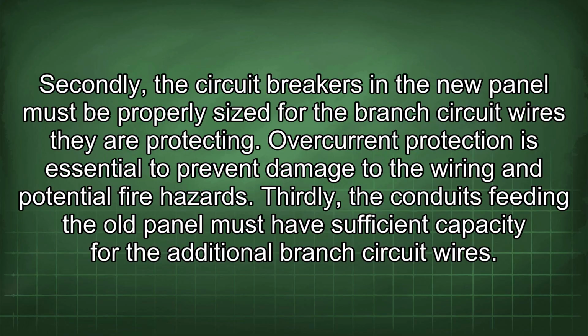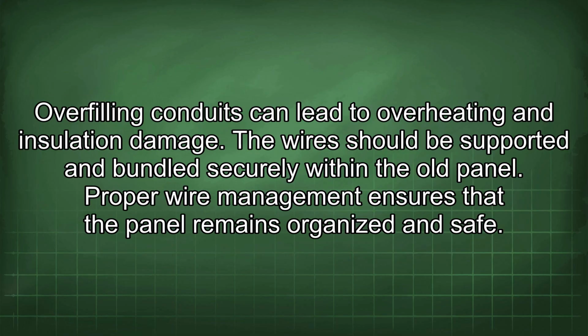Thirdly, the conduits feeding the old panel must have sufficient capacity for the additional branch circuit wires. Overfilling conduits can lead to overheating and insulation damage. The wires should be supported and bundled securely within the old panel. Proper wire management ensures that the panel remains organized and safe.